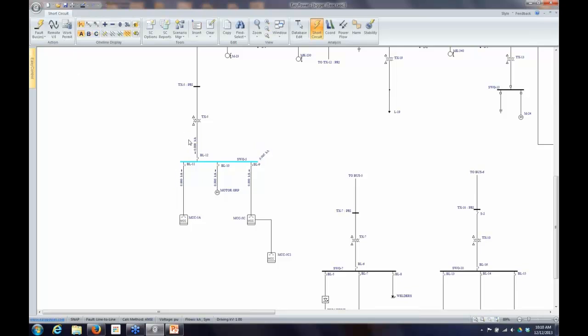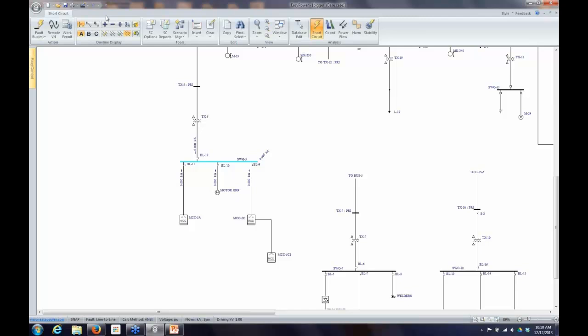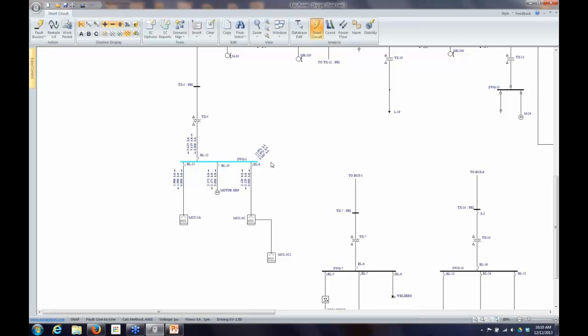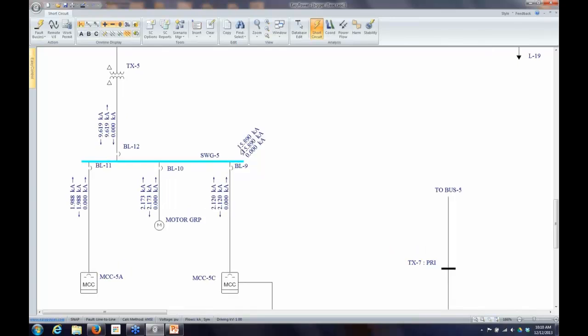Rather than displaying phase currents, I can display the sequence currents. EasyPower uses symmetrical components to do all of its fault calculations, so it has knowledge of the positive, negative, and zero-sequence fault currents. I can look at the positive sequence, negative sequence, and zero-sequence. For a line-to-line fault, positive and negative sequence are the same, and zero-sequence is zero. Three I-zero is also going to be zero for a line-to-line fault.